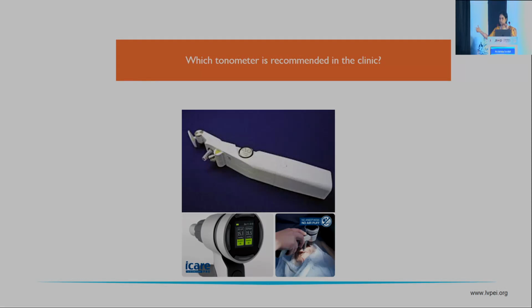We use it maybe after 5 or 6 patients. One thing we should avoid is holding the probe and trying to clean it. If you do that, the metal at the back is going to be affected. Even a small misalignment can make your readings seriously erroneous. So sometimes we see IOPs of 40, 50 recorded from the pediatric clinic, and they come to you.